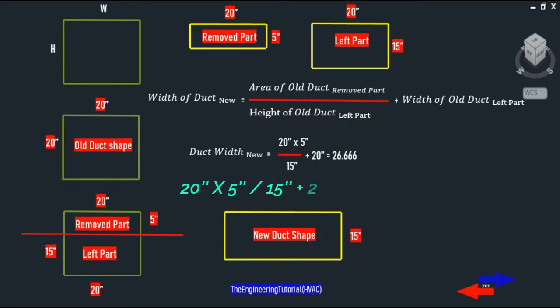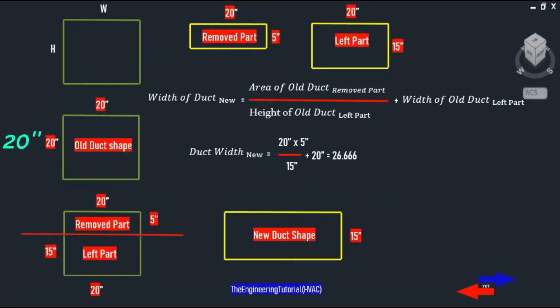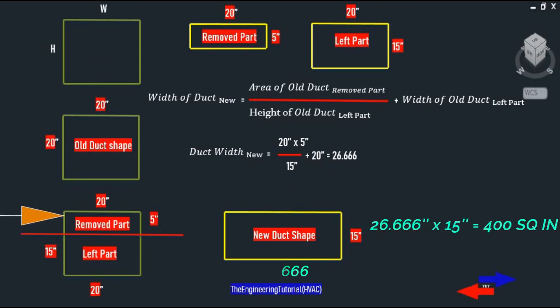So: 20 inches times 5 inches divided by 15 inches, plus 20 inches, equals 26.666 inches. As you can see, we've decreased the height of our old square duct from 20 inches to 15 inches and increased the width, changing its shape from square to rectangular.